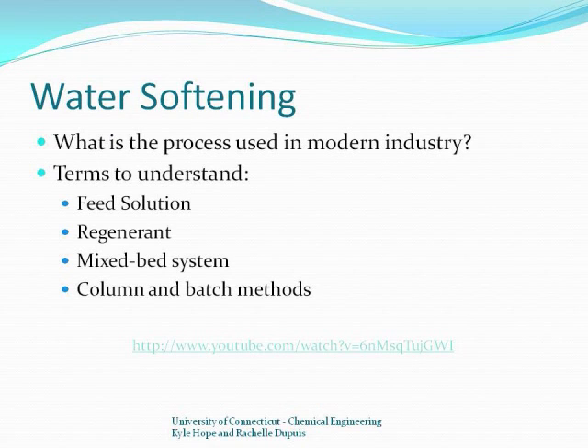Now that we know what chemical reaction is taking place, we can study the actual process. A feed solution simply refers to the solution being purified, deionized, or softened. It is fed into a large stainless steel or reinforced fiberglass tank where, depending on the application, it passes through either a series of beds or a mixture of exchange resins. In a batch system, which contains hundreds of liters of cation and anion exchanges mixed together, the solution flows through and simultaneously exchanges positive and negative ions.